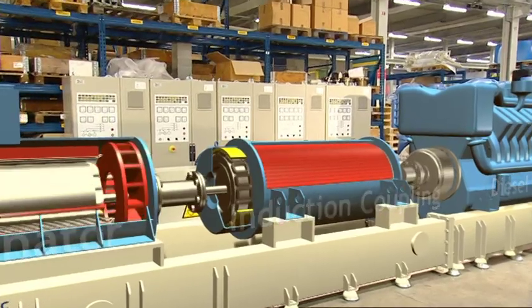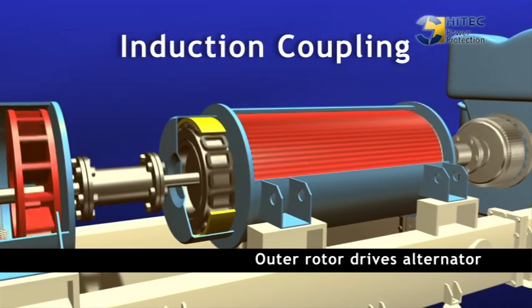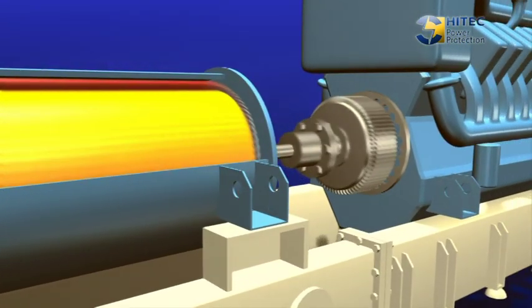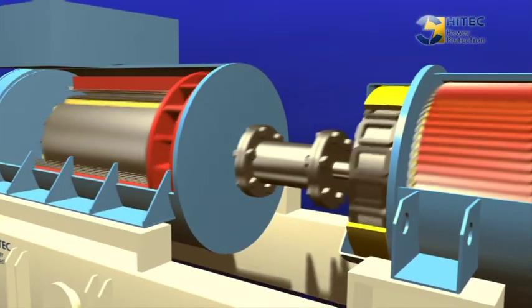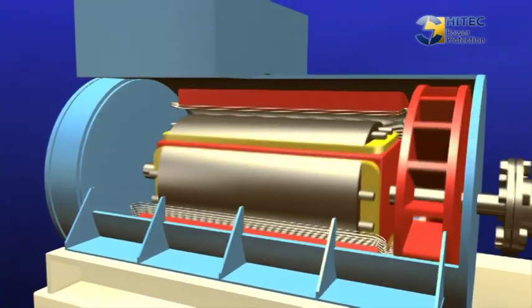The so-called induction coupling — the UPS system runs in parallel with utility power supply, always ready to take over the load if needed. The induction coupling has an outer rotor running at the same speed as the alternator and a free-rotating inner rotor running three times faster than the outer rotor to store kinetic energy. In combination with the choke coil, the alternator functions as an active filter for voltage peaks, frequency variations, brownouts, and harmonic distortions.